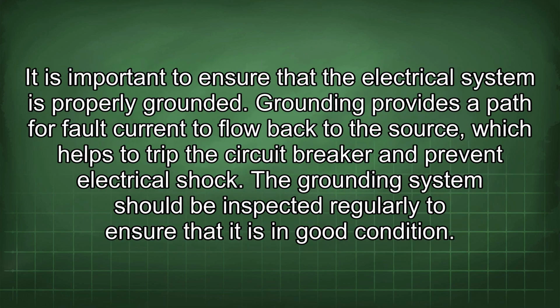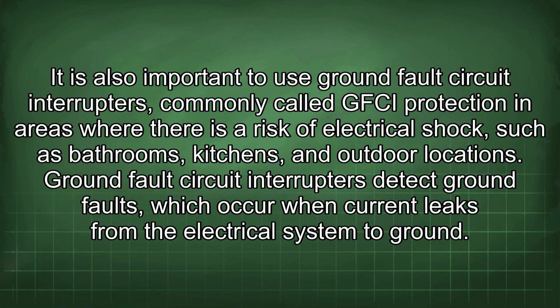It is important to ensure that the electrical system is properly grounded. Grounding provides a path for fault current to flow back to the source, which helps to trip the circuit breaker and prevent electrical shock. The grounding system should be inspected regularly to ensure that it is in good condition. It is also important to use ground fault circuit interrupters, commonly called GFCI protection, in areas where there is a risk of electrical shock, such as bathrooms, kitchens, and outdoor locations.